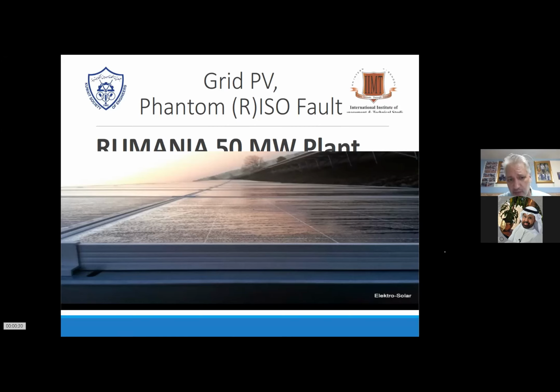So during that time, when you have the condensing water on top or bottom of the modules, you will encounter that the inverters will stop producing or show isofaults or show some numbers depending on the manufacturers. And this phenomenon has got nothing to do with the modules, nothing to do with the inverter, and also nothing to do with the cables.